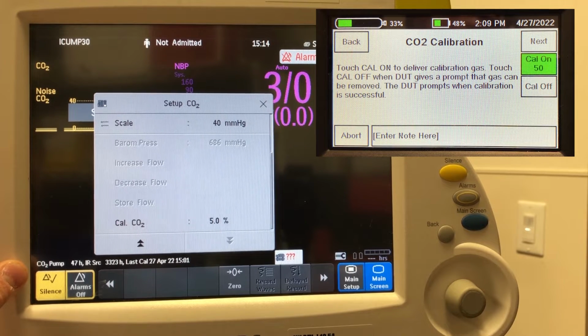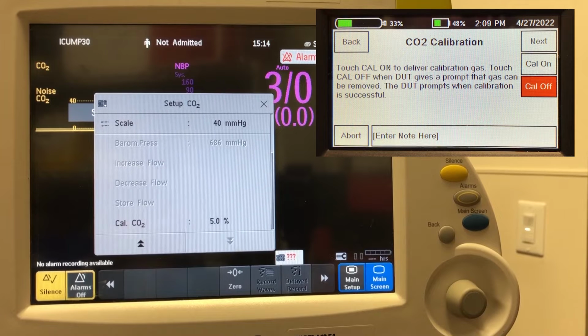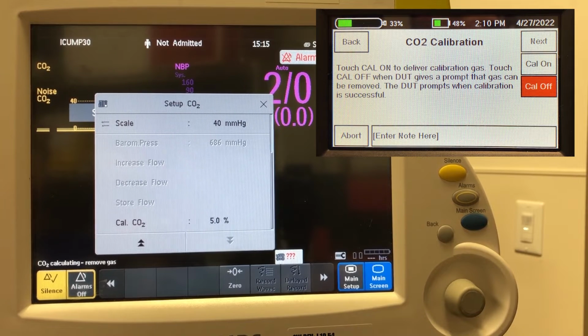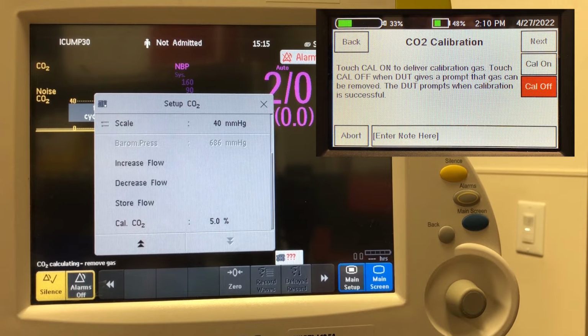So we watch this message here, and it just beeps, so it means it's probably ready for us to turn off cal gas. It says remove gas, so we can turn it off over here. And now we wait for the monitor to finish its calculations, and over here it'll stop saying remove gas and start telling us that it was calibrated on today's date. That beep tells us that it's almost done, I believe. There it is, CO2 calibration done. So we can hit next.